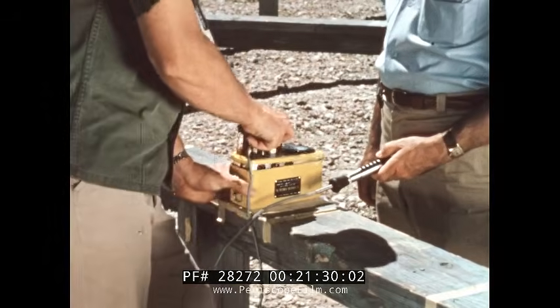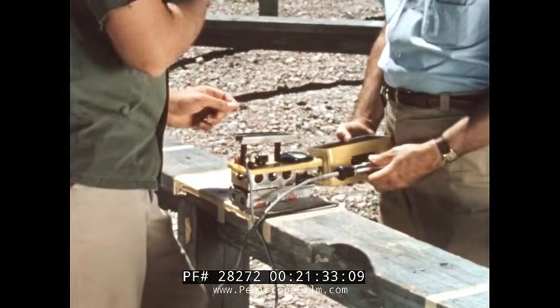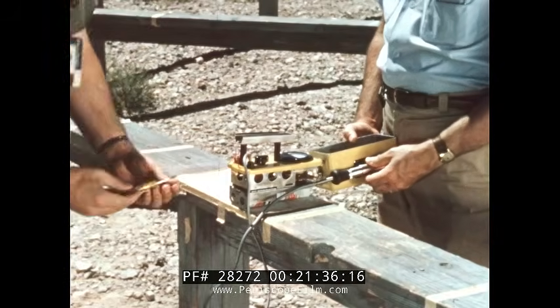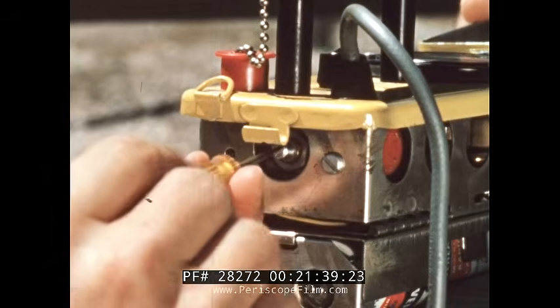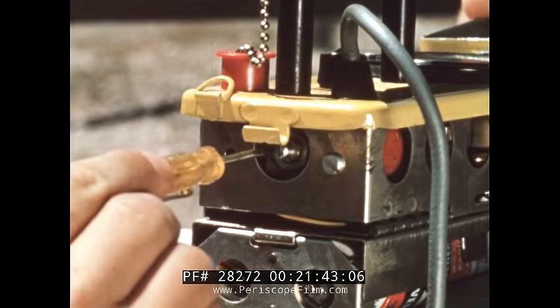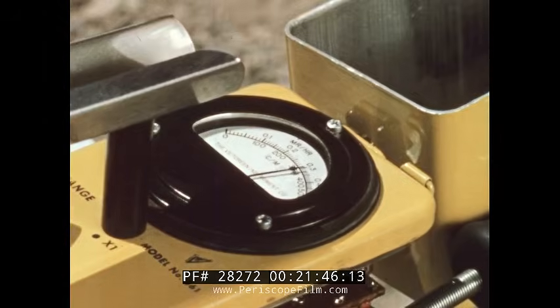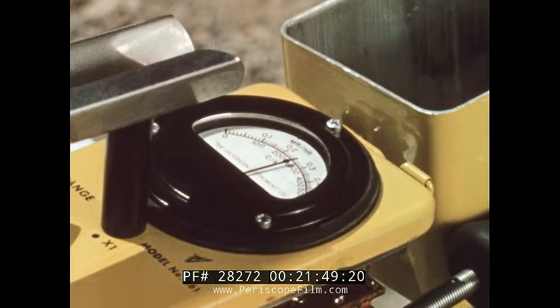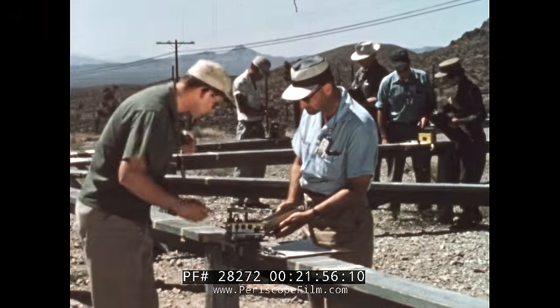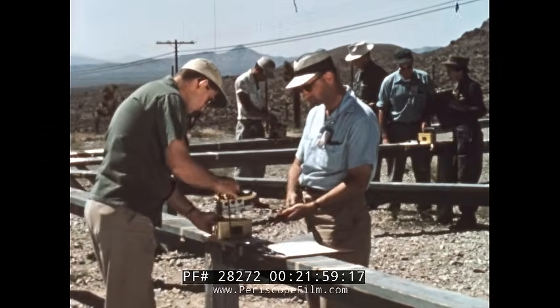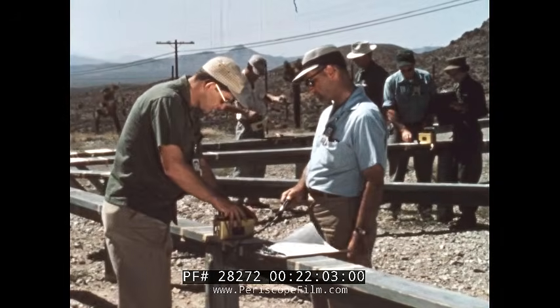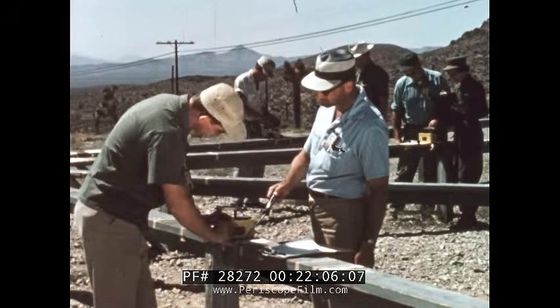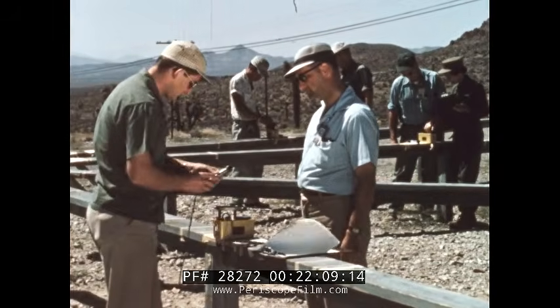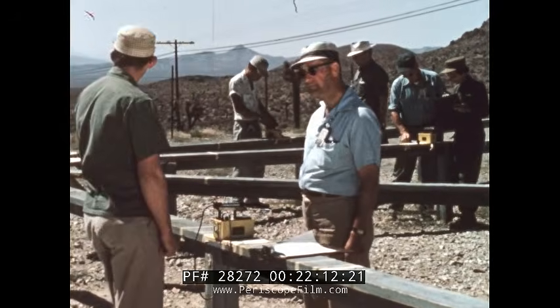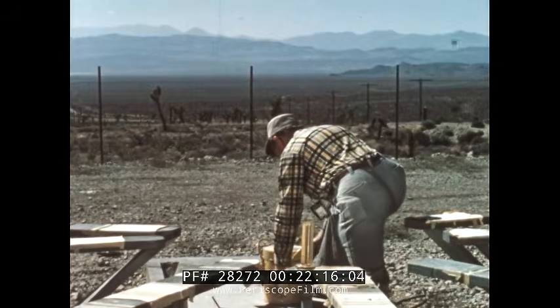If the indicator falls above or below this range, the instrument is removed from the case and the calibration screw adjusted. Rotating the screw clockwise increases the reading, while counterclockwise rotation decreases it. When the instrument is reading properly, it is returned to its case and the beta shield is closed. If the instrument does not respond to this procedure, it will not calibrate properly and should be repaired. The completion of these steps by all monitors is the signal for a known intensity source to be placed on the range.